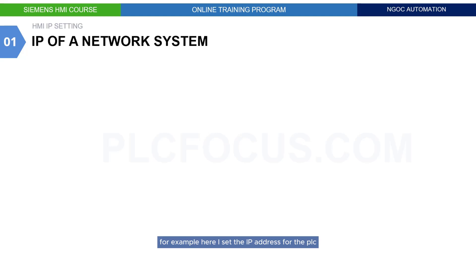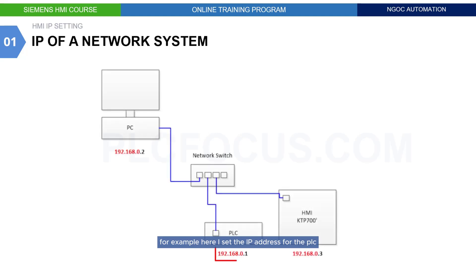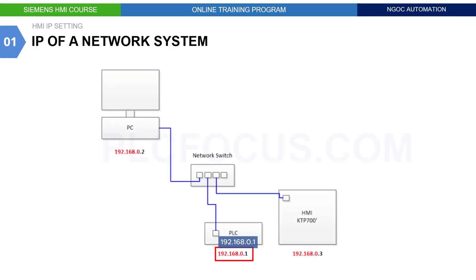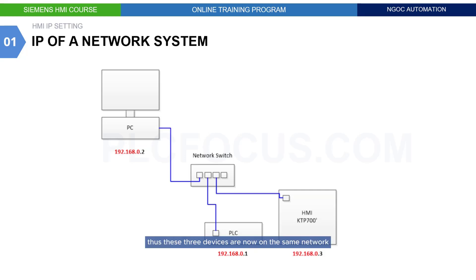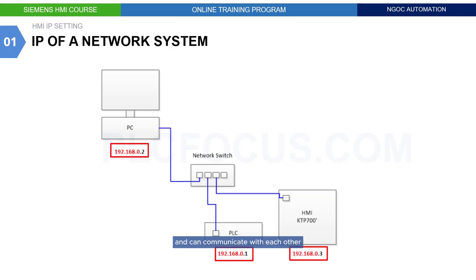For example, I set the IP address for the PLC to 192.168.0.1, the computer to 192.168.0.2, and the HMI to 192.168.0.3. Thus, these three devices are now on the same network and can communicate with each other, provided they are connected by network cables.